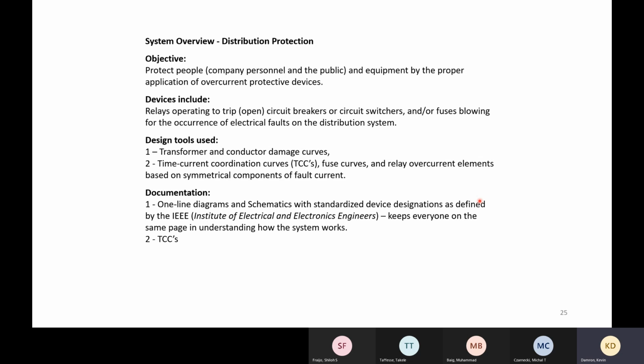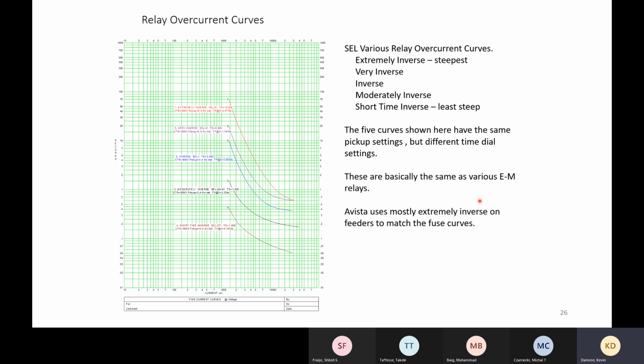So the way we do that, we trip circuit breakers and circuit switchers, or fuses, and we use a thing called a TCC. It's a time current coordination curve, and we use it to look at coordination between 51 elements. This is what a TCC looks like for those of you who've never seen one. On the x-axis, it's a log scale, and we've got amps. Sometimes you'll see this as multiples of pickup instead of amps, but amps is a little more common. And then along the y-axis, we've got seconds, again in a log scale.